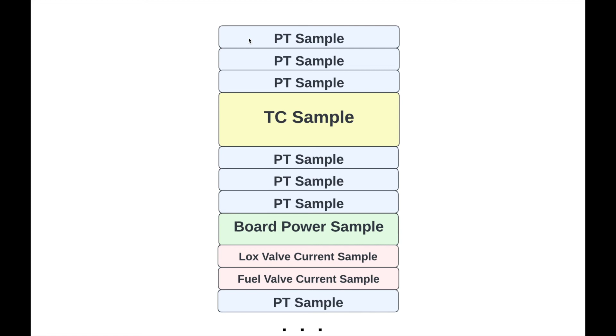In the case of our PTs, at this point the microcontroller has received a number between 0 and 65,535 from the 16-bit ADC. This number doesn't really mean anything yet, so the code takes this number and does a simple interpolation to determine what pressure that corresponds to, between 0 psi and 1,000 psi. This is the final step of that information being processed into the number we're trying to understand about the physical system. Each of the sensors goes through a different process, but the idea is the same: taking that raw information into the microcontroller and processing it into the final data we understand as the physical characteristic.